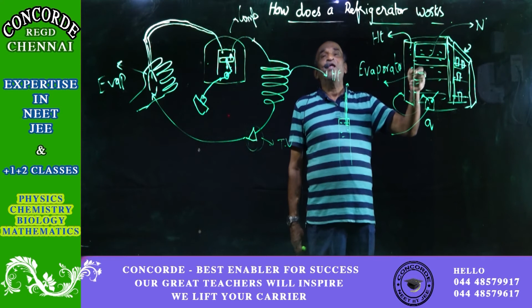Now, after the capillary tube, at very low temperature, with 10 or 15% vapor form and the remaining 90 to 95% liquid, it enters into all the different tubing on the back side and also at the top and bottom side. Circulation takes place, which you cannot see because this is all covered. Because of that circulation, cooling takes place. Then after the cooling, when the heat is taken by the ether, bodies will get cooled. So ether will be at a slightly higher temperature than the cold bodies. It will also be in the vaporous form, because when it takes the heat, it becomes a vapor. That vapor now enters into the compressor, and everything that I have told you is just repeated again and again, so that continuous cooling is taking place.